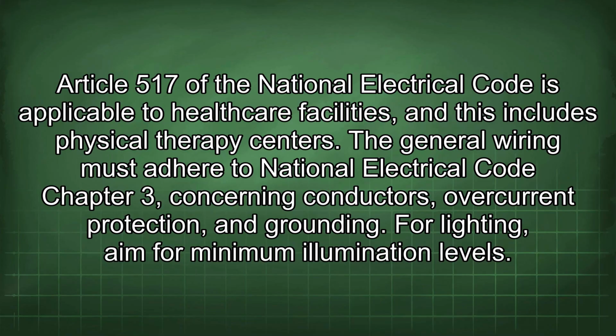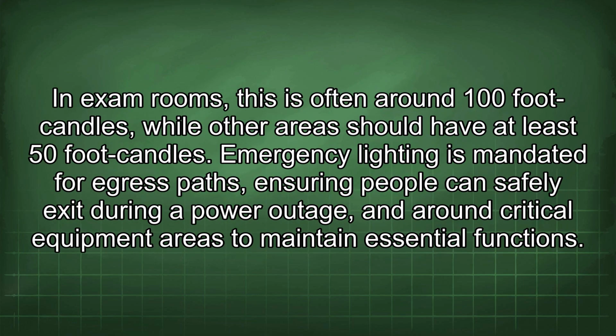Article 517 of the National Electrical Code is applicable to healthcare facilities, and this includes physical therapy centers. The general wiring must adhere to National Electrical Code Chapter 3 concerning conductors, overcurrent protection, and grounding. For lighting, aim for minimum illumination levels. In exam rooms, this is often around 100-foot candles, while other areas should have at least 50-foot candles.